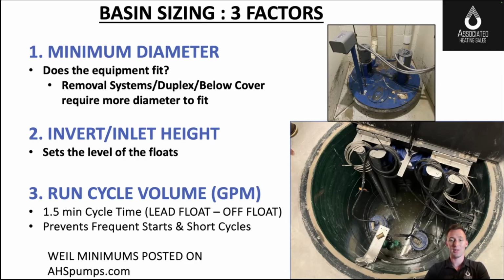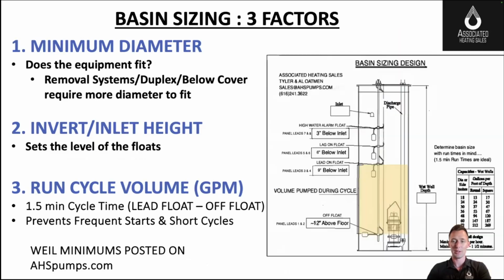The first consideration is just what we're talking about. I know what pumps I want to use. Does everything fit? So you have a minimum diameter. And you can see how we're right up against it sometimes on our designs, which is fine. And then here's a room that has no real room for more diameter either. So a couple considerations there on your side and my side of it. The next two are leading us to how much runtime does a pump have when it turns on for its cycle. So let's just look at this.